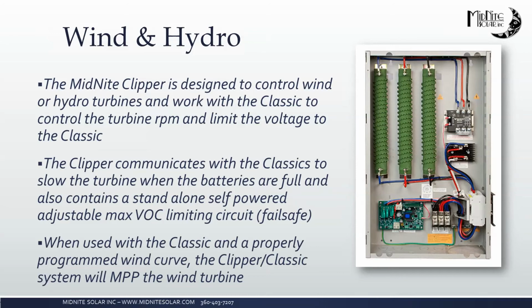So what the clipper is designed to do is basically go in between those turbines and the classic. And it's designed to act as a fail-safe, an emergency brake, if you will. It's self-powered, it's self-regulating, so at the very first stage, it's going to make sure that it never lets through too much voltage for the classic you're running. And after that, it's also going to talk to the classic, and the classic's able to use the clipper to throttle the turbine down so there is not so much energy. We can actually slow it down, even stop it, to the point if there's some solar in the mix as well, you might look out and see the turbine's not even turning, and that's because the solar is able to keep up and we don't need to wear the turbine out.